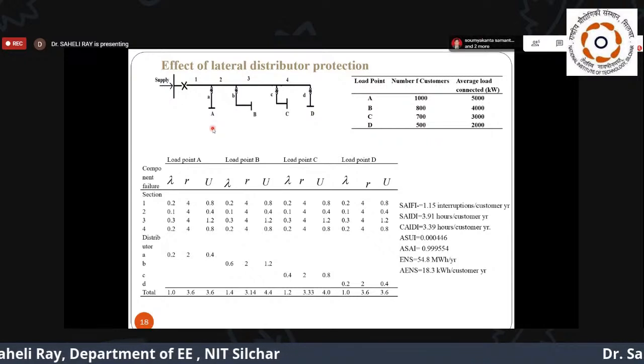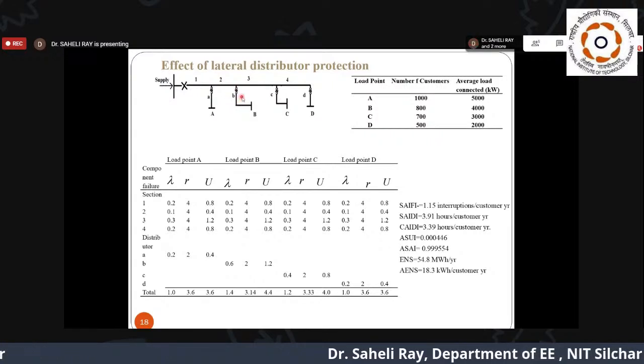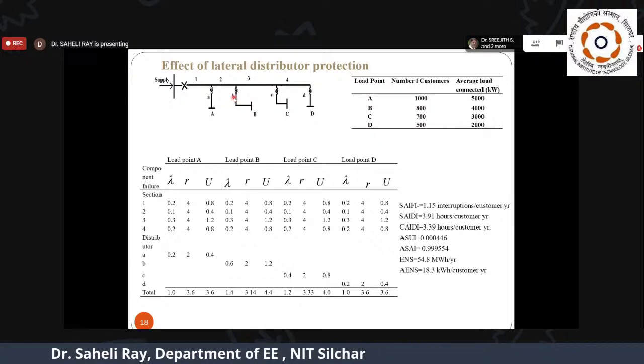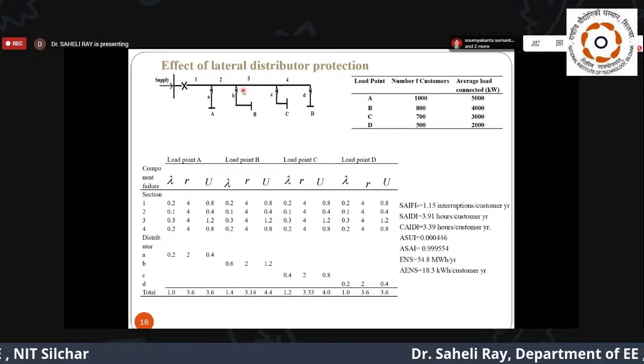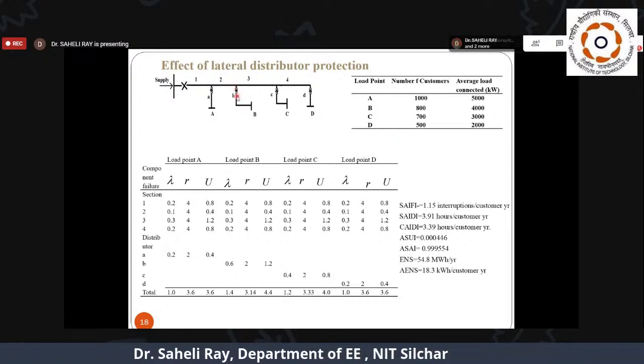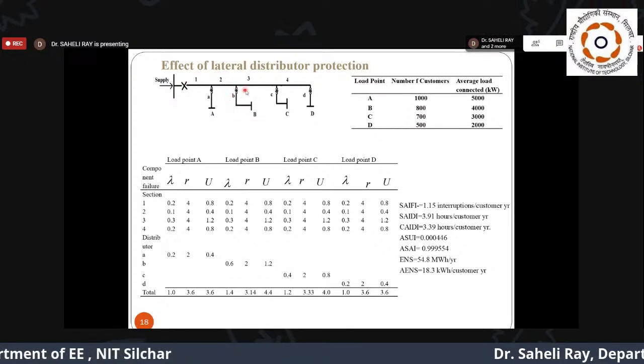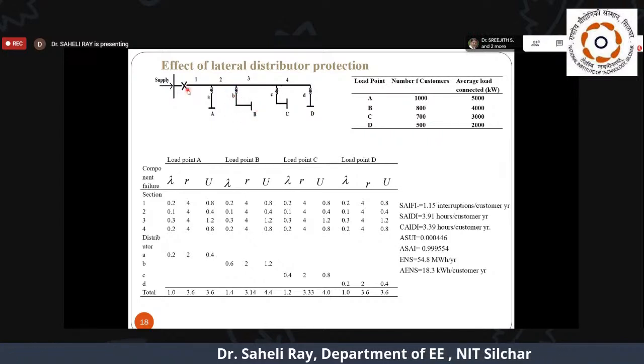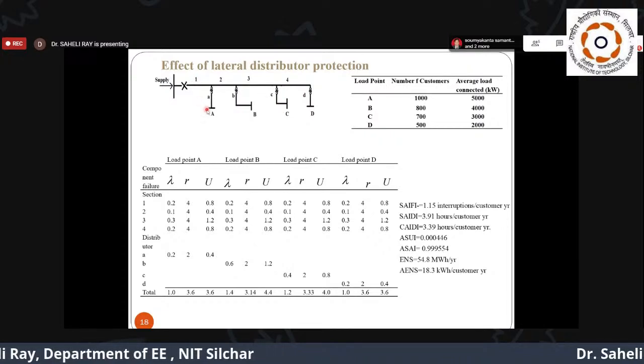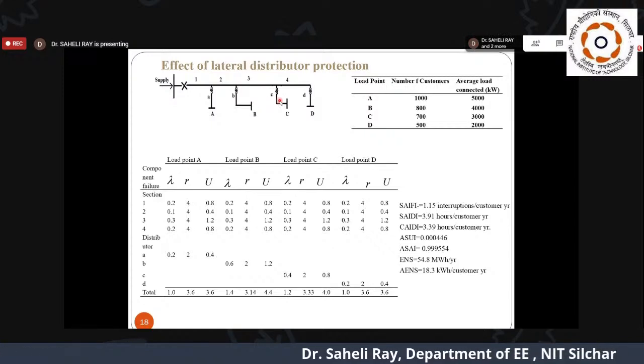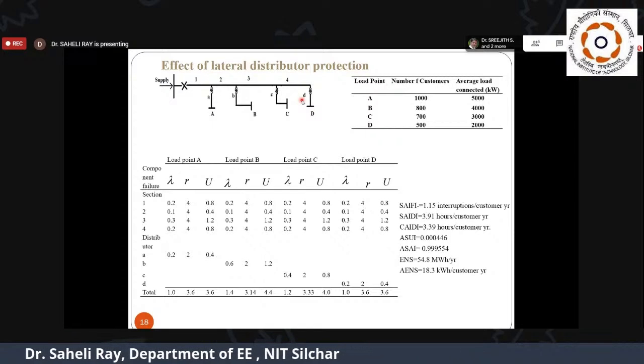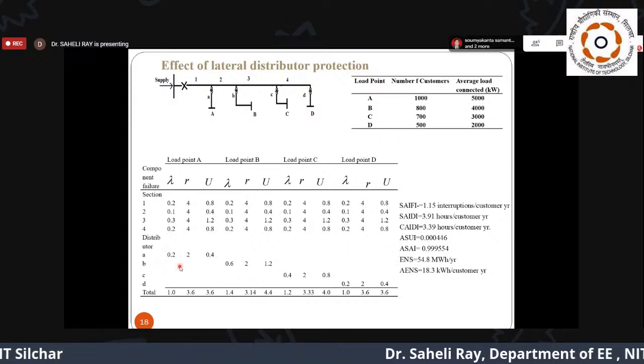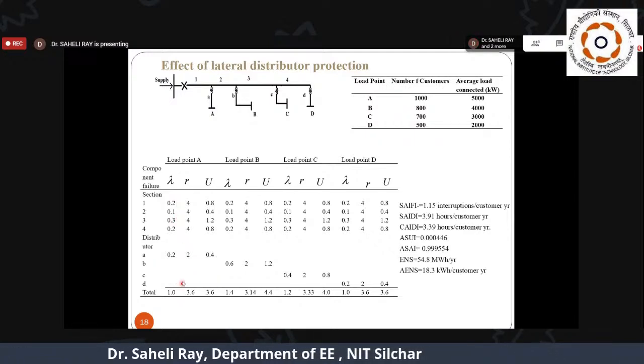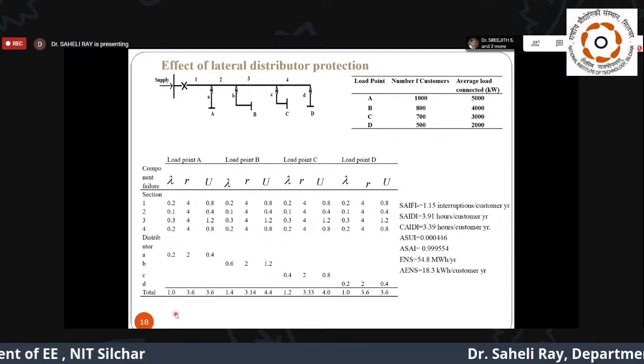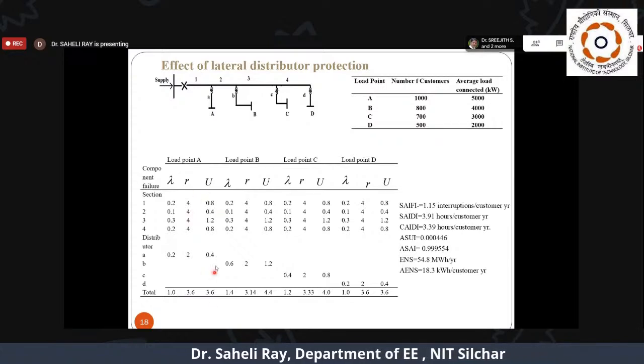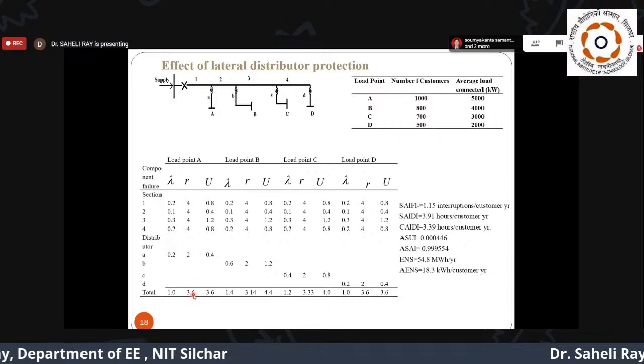But on the contrary, suppose a fault occurs at load point B. Then what will happen? Since there is a fuse over here, this fuse will disconnect. It will disconnect this faulty portion from the healthy portion, and the whole portion after the fuse will be disconnected. This is the faulty portion, and the other portion of the network will not be affected. The same will be the case if there is a fault in C or in this portion D. That's why the effect of laterals B, C, and D does not come into this picture. As a result, the average failure rate will reduce. This is a sign of improvement. Annual outage duration will also change, and the average repair time will also change.